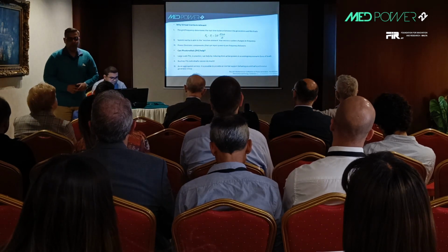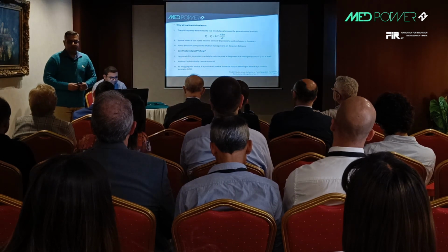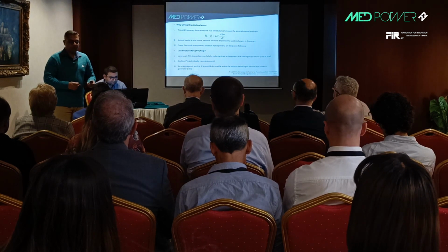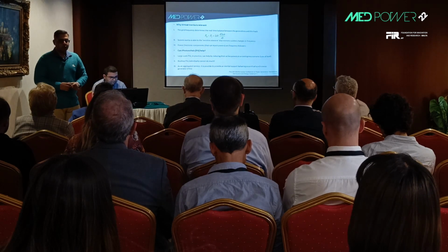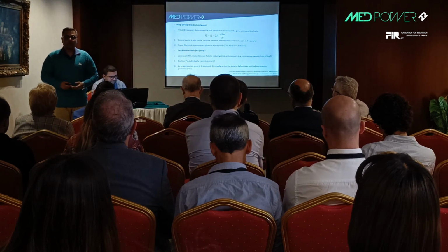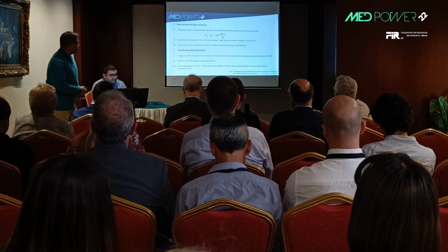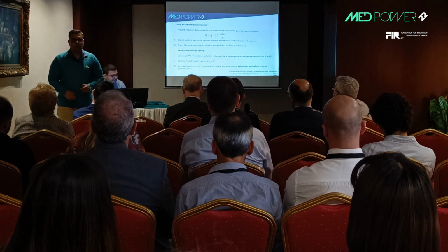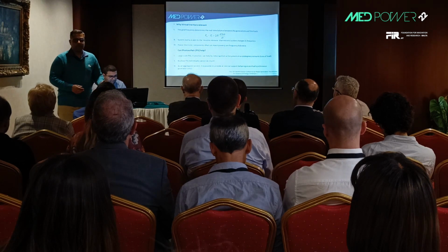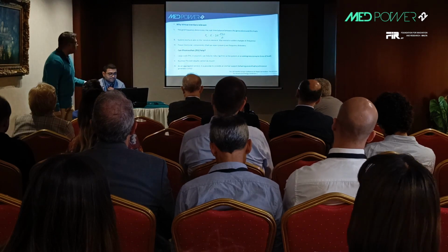For example, if a grid goes into maintenance, the PVs are no good because they are not getting any frequency command. So the PVs also turn off unless there is a DG, a diesel generator, or any other frequency supporting source. So a PV as a virtual synchronous generator can perform black start capability if it is designed in such a way. And of course, if the load and the insolation allow such a scenario, the PV can act alone as a virtual synchronous generator.